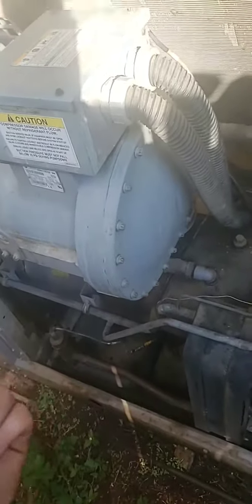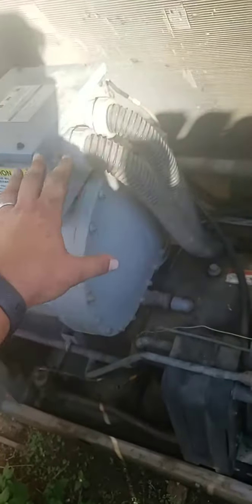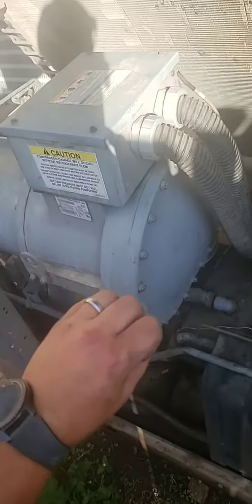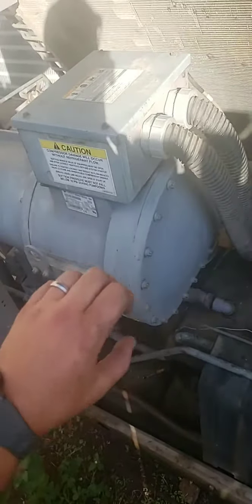And so we energize either one of these valves to slide that slide back and forth using the discharge pressure and the suction pressure, manipulating them, just like a reversing valve, how we energize it and use discharge and suction to move a reversing valve back and forth. Well, we do the same thing with this slide valve and those two relay or solenoids. We're using our system pressures to push that slide back and forth. So if you had a compressor like this that wasn't staging up properly, you may have an issue with those solenoids, or the slide itself sometimes can actually stick and it won't be able to move.